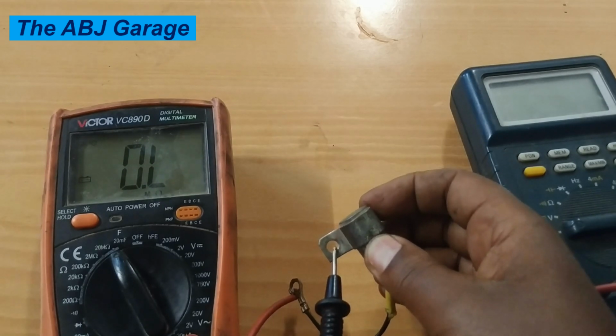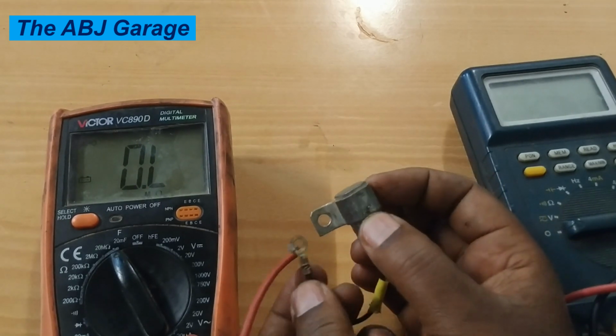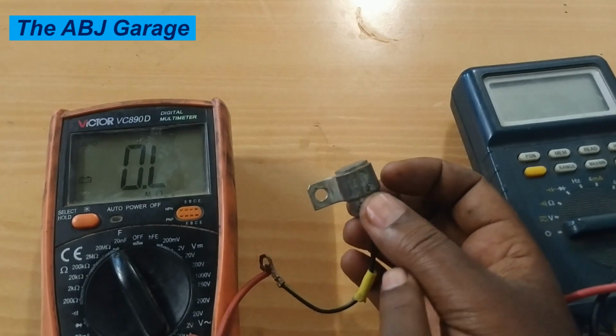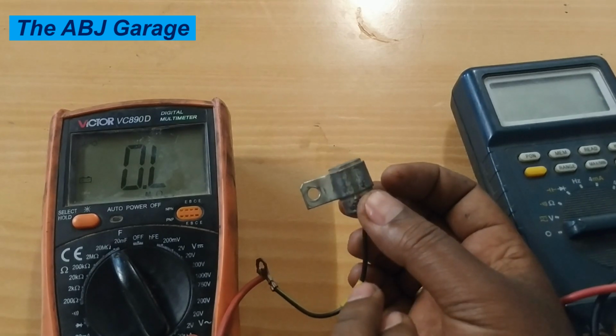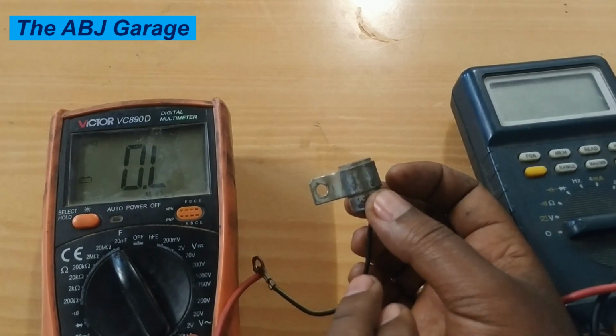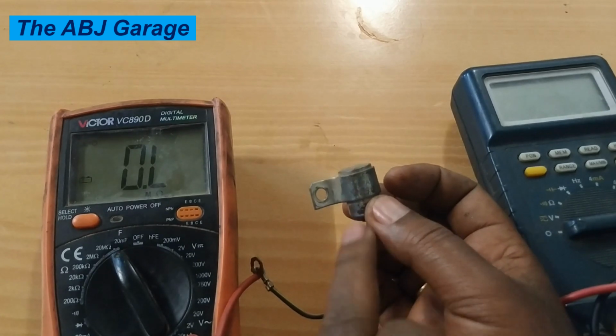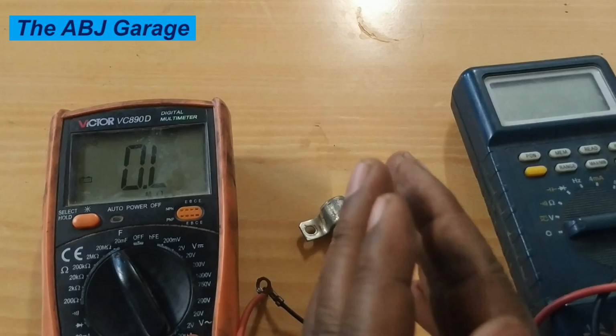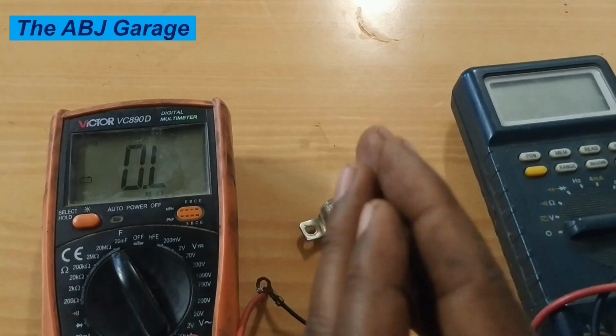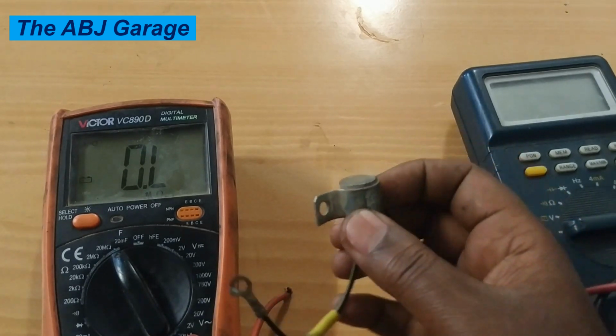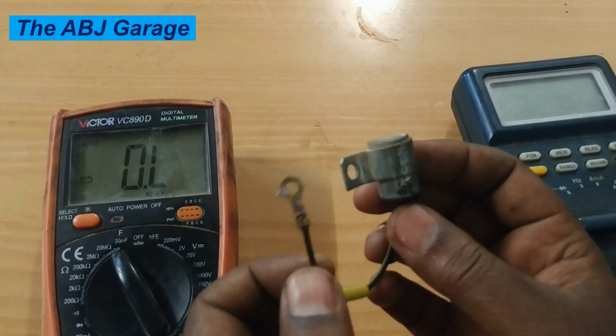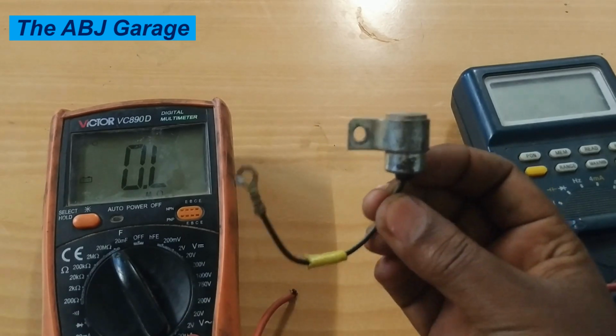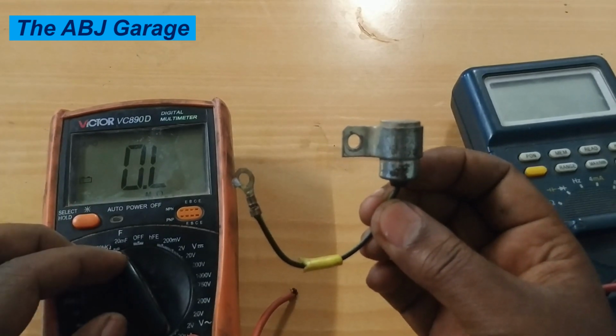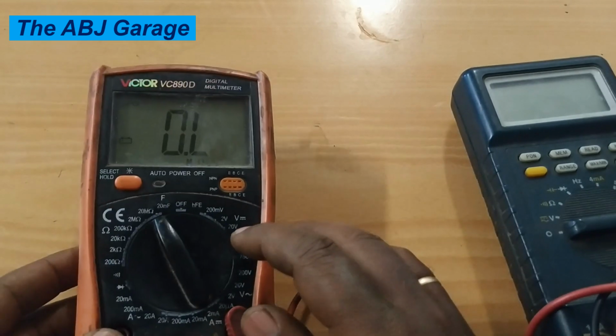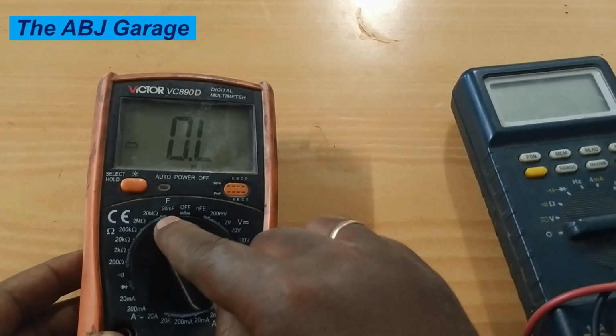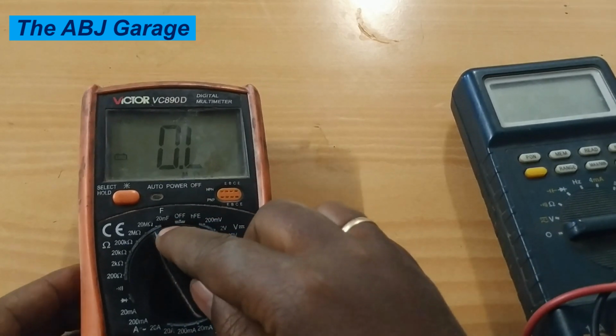See? It has gradually increased from some value to infinity, which indicates that this capacitor is receiving charge. It has passed the resistance check. The resistance has to be infinity, since the capacitor terminals should not be touching each other. The gradual increase of the resistance value shows that this capacitor is being charged by the multimeter battery. So on this type of multimeter, put it on the maximum resistance value, which is 20 mega ohm for this particular multimeter.